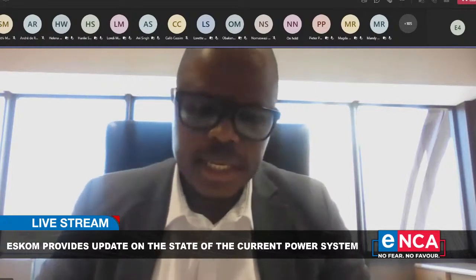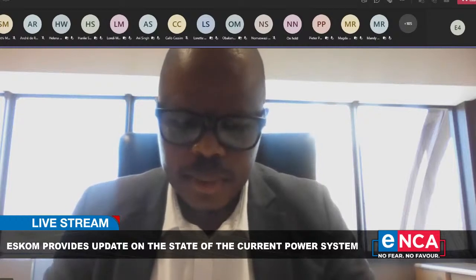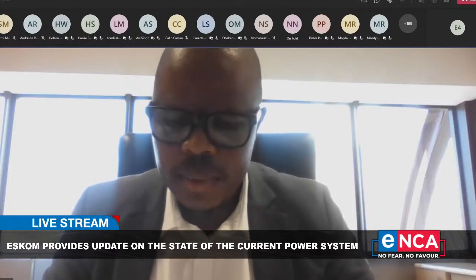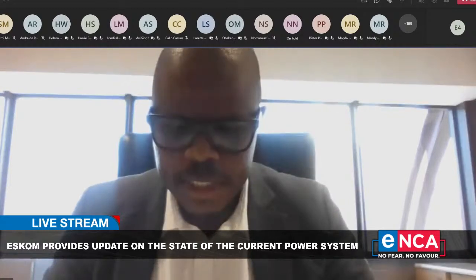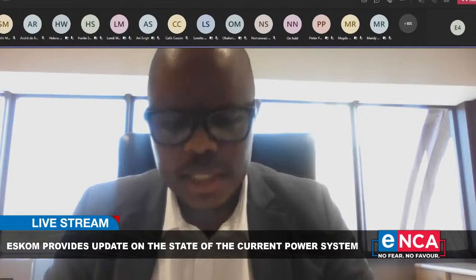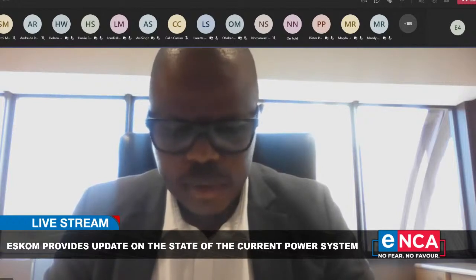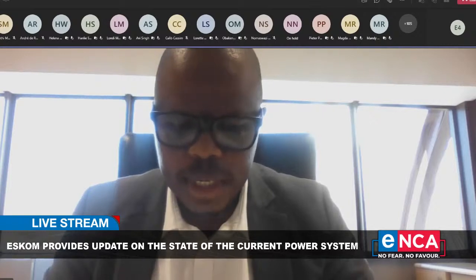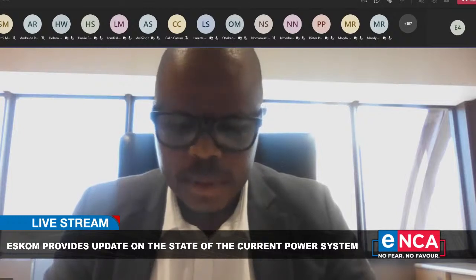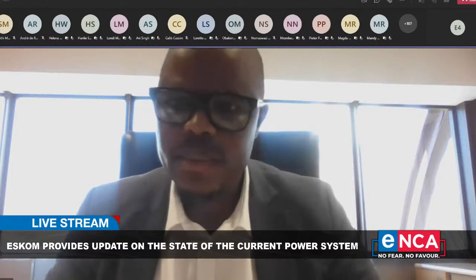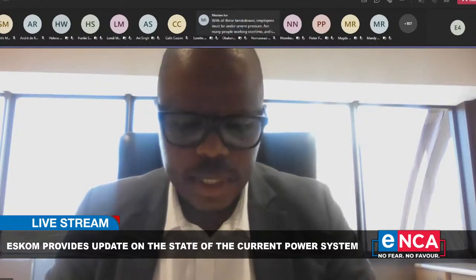Okay, at Kusile, we are having a boiler tube leak on our unit number 1. Yesterday, which is on the 16th, at about 8:30, we received the suspicion of a tube leak from our operating staff, and they called our engineering team to come and investigate and confirm if indeed it is a tube leak. After the investigation, it was confirmed that there is a tube leak at about 63-meter level on the area between the evaporator and the superheater inlet area. So we then deloaded because the steam was coming out of the lagging and cladding at around 70-meter level. And then at 15:30, we shut down the unit in order for us to do the repairs.